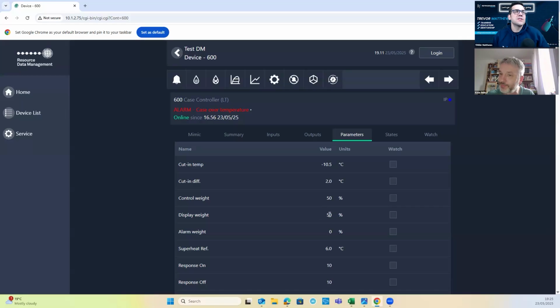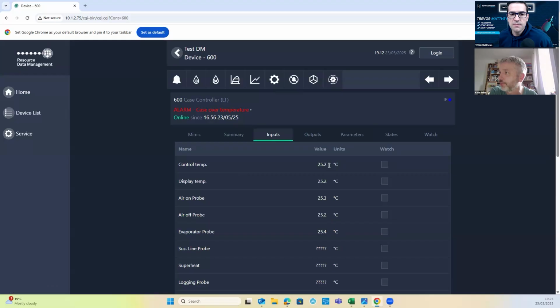Right. Okay. Can we just go back through that one more time? Because this is different than a lot of controls that people would see. When you say control weighting, that means air on. Is that correct? So it depends what you set it to. So control weighting is where it's getting its control temperature from, right? So where it's 50-50 at the minute, it's taking the air on and the air off, and it's using 50% of each, if you like. So it will be the average of the two, effectively. It'll be right in the middle.